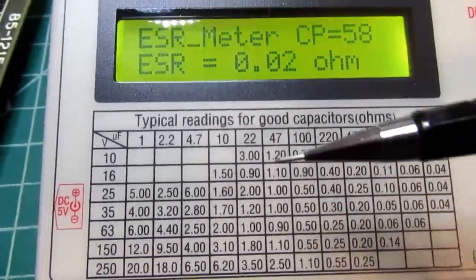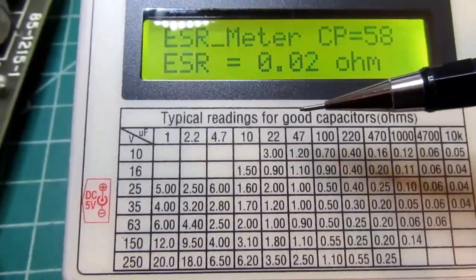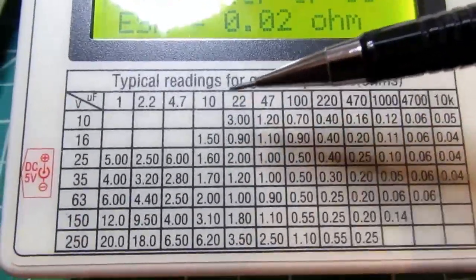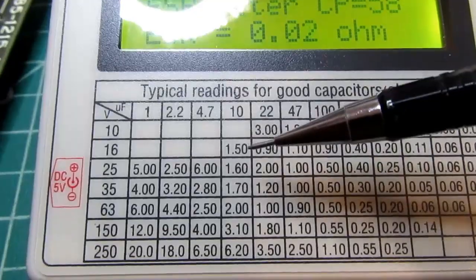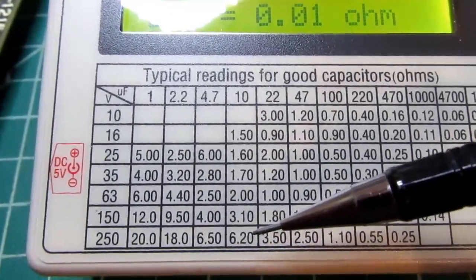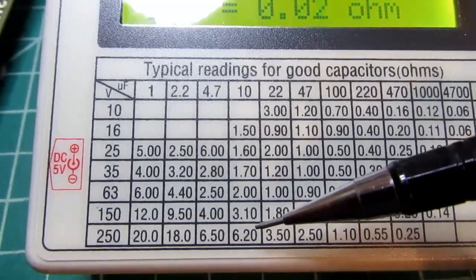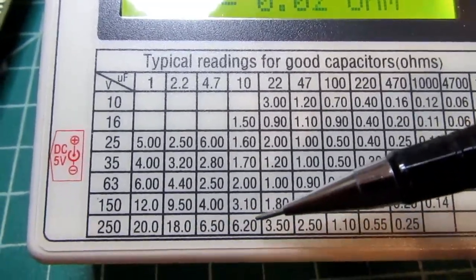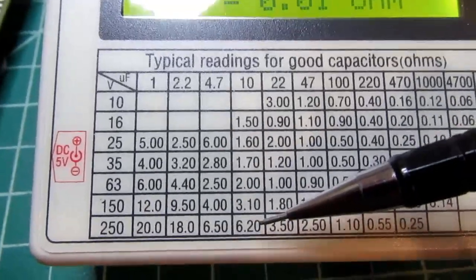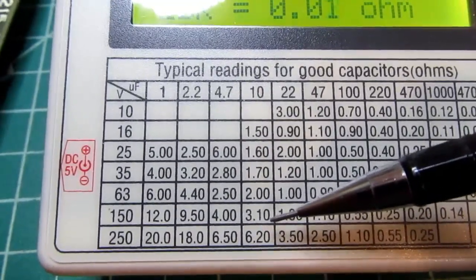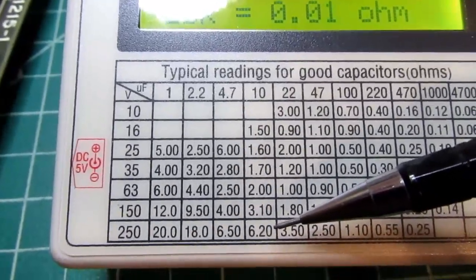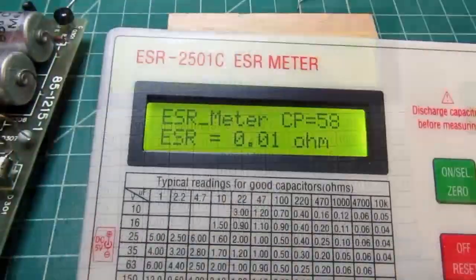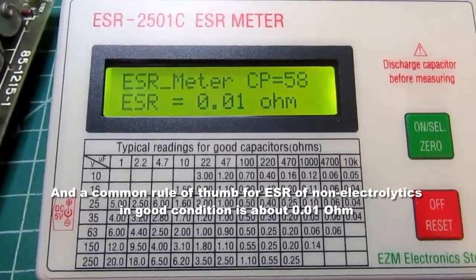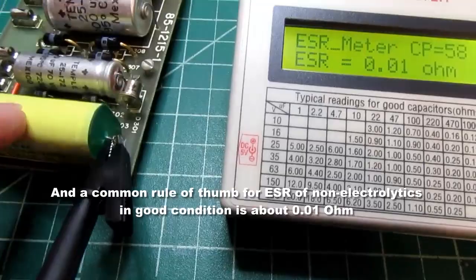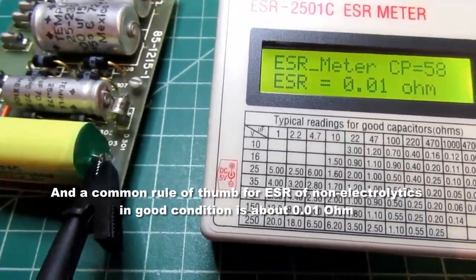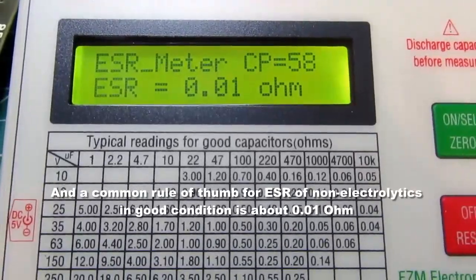Let's check the chart, which is really oriented towards electrolytics, but let's go with 8, or round to 10 microfarads, down to 250 volts - you could use 150 or 250, equidistant to the actual 200 volts. It's suggesting the ESR could be as high as 6.2 ohms, and this is reading really small. But ESR is typically higher on electrolytics than on other types of capacitor, where it's usually much smaller, so it doesn't surprise me this is such a small value.